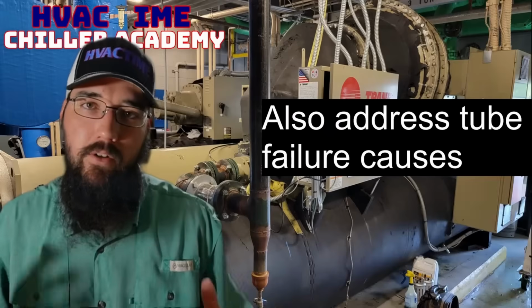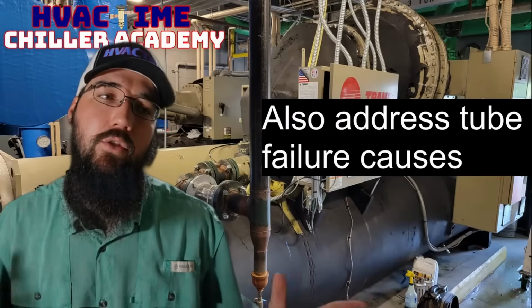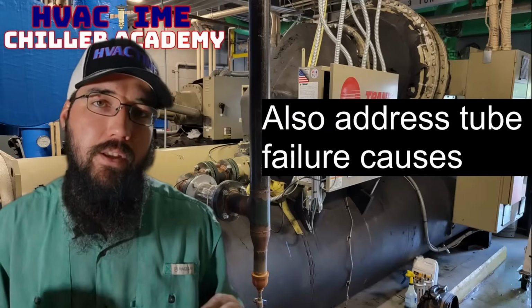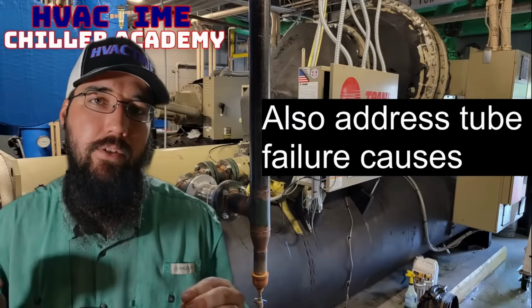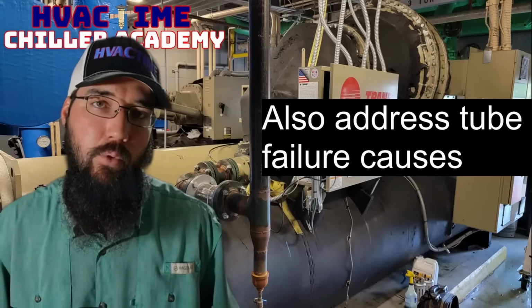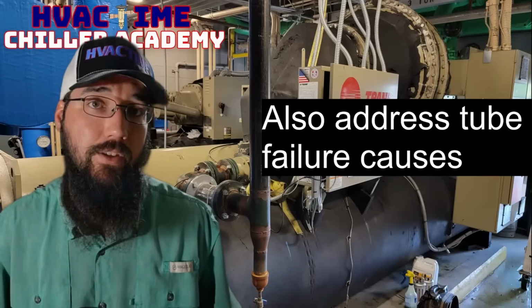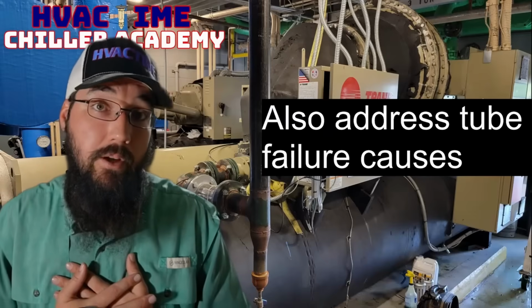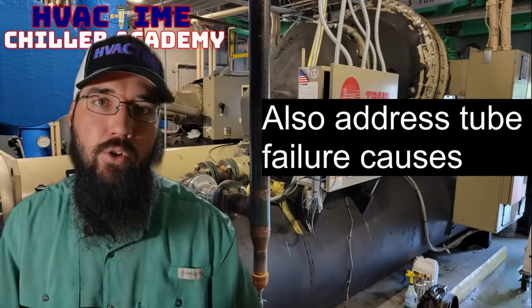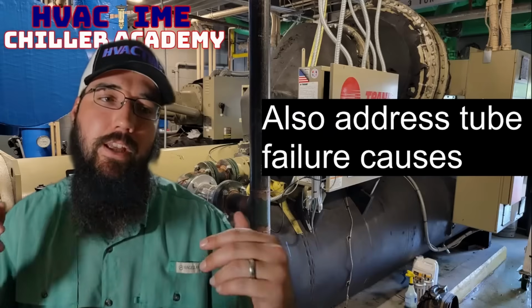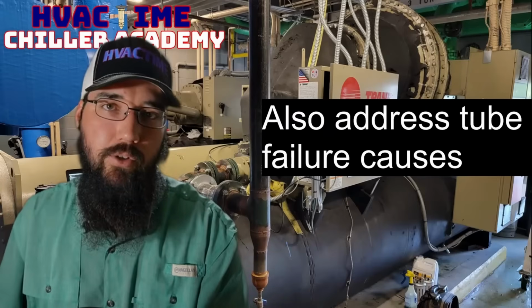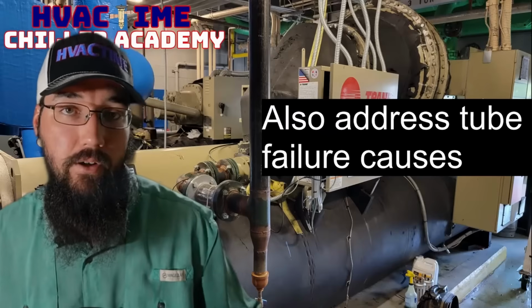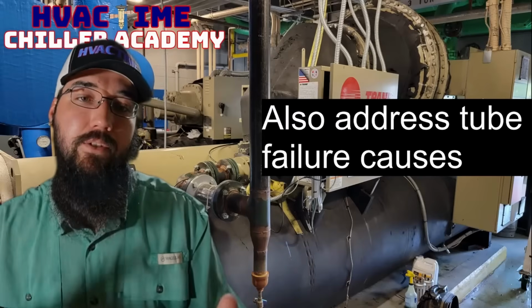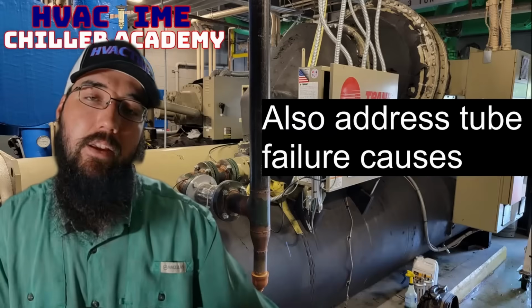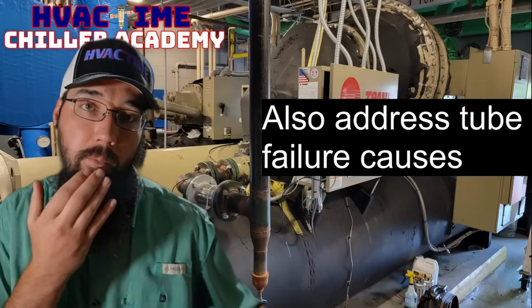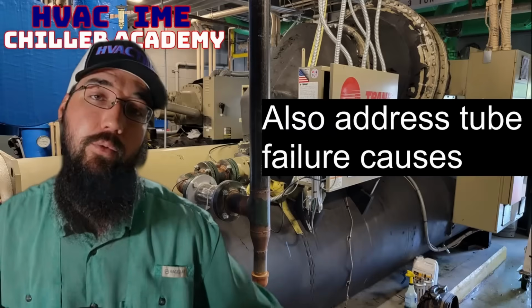In that event, you've got to do a complete overhaul of that entire machine. So if it was that bad, more than likely it's going to be worth it to have the machine retubed at that point. And there are companies out there that specialize in this. I personally have not done a retubing myself. Unless you have a team internally to your organization that does that, there are some really good companies out there who do that very, very well. In the process of trying to rebuild this machine and put it back together, it's going to be recommended to do a retube. And if you're going to do a retube, you're going to redo all the tubes.